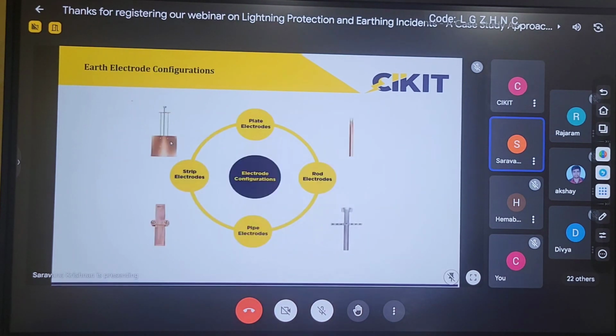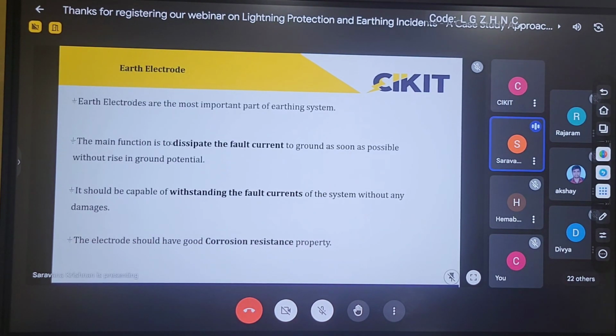So the main purpose of this electrode which we are using is to dissipate the fault current. So if I'm having the earthing, the current starts dissipating into the soil. But before this current enters into the soil, the entire current will be flowing through the particular conductor alone. So the conductor should be able to withstand the current, and only if it withstands can the current be dissipated into the soil. So if I am not providing proper conductor sizing, then the conductor itself will break because of the huge heating. As we know, there will be power loss, heat loss, I squared R.